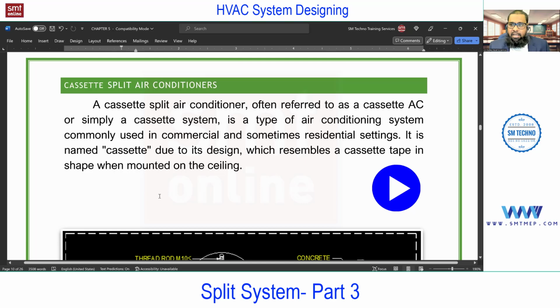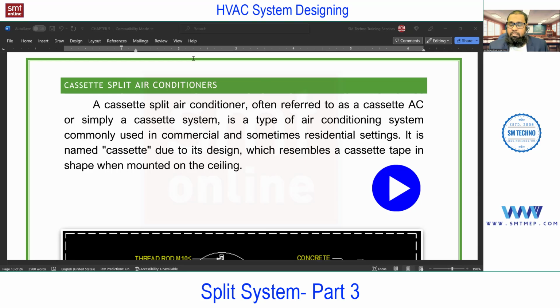This is the second type of split AC, and this is a ceiling suspended type. Sir, what about the location of the outdoor unit? If the outdoor is on the ground and the indoor is at the top, is there a gravity effect on the flow of refrigerant? It's a closed system, no? Anyhow, other parameters will affect. So that's the reason the position of this unit is important, and according to that, from the vendor catalog, you'll get the exact information.